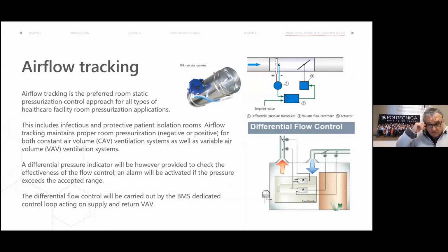Airflow tracking, of course, to provide the pressure inside, negative or positive. The way is to control the airflow that is supplied to the room and the airflow that is extracted from the room. This is made by VAV systems, variable dampers, that are controlled by BMS. Of course, if you want to have an under pressure, for example, like in the COVID-19 intensive care unit, and as it is described in this sketch, you see there is the air that infiltrates under the door and enters inside. So we have an extraction which is higher than the supply, and in this case you will have an under pressure inside here.